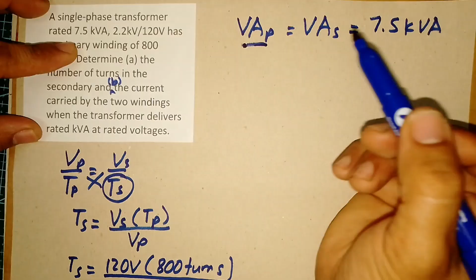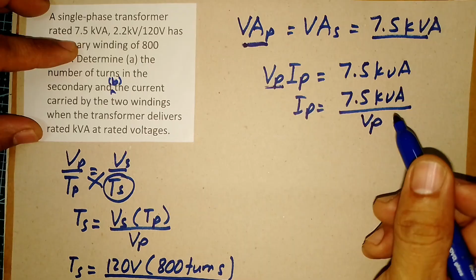So these two are what we'll take. Therefore, the voltage of the primary multiplied by the current of the primary equals 7.5 kVA. Let's cross-multiply the voltage of the primary to the other side of the equation. So we have 7.5 kVA divided by the voltage of the primary. Let's not get confused - this is 7,500 volt-ampere.